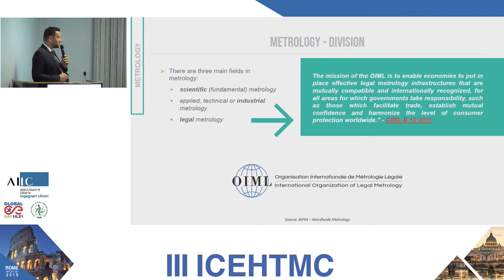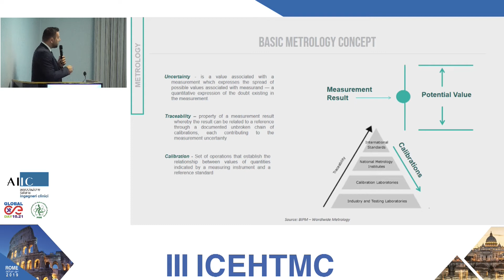When we are talking about the basic concepts of metrology, there are 3. The first one, uncertainty; second one, traceability; and calibration. Only those 3 things are already talking too much in comparison with anything else that was before. Just implementing those 3 things. Because if you have uncertainty, you know exactly where you are with your measurement. If you have traceability, then you can see where you are in comparison with the definitions and everything else. And if you have calibration, it will prove that you have both of those 2.